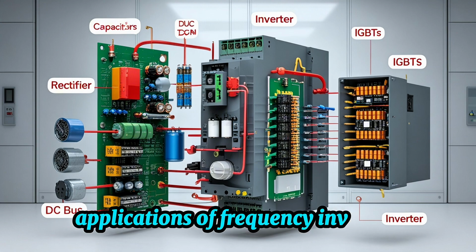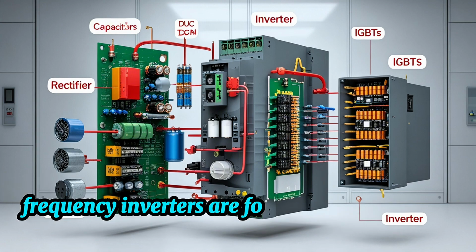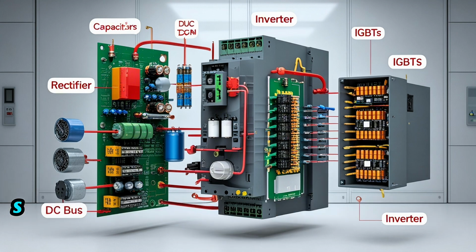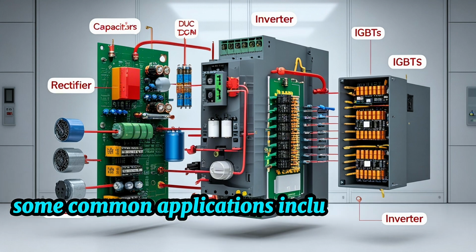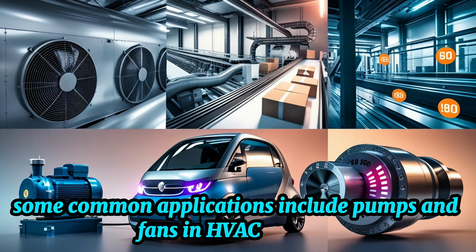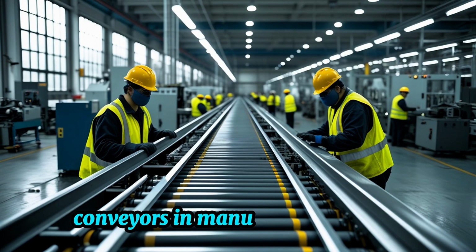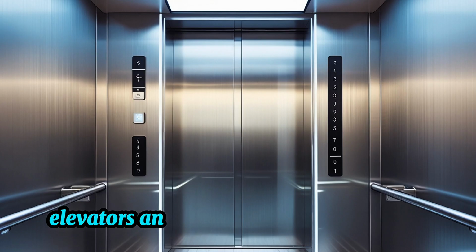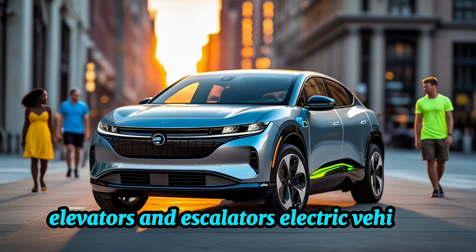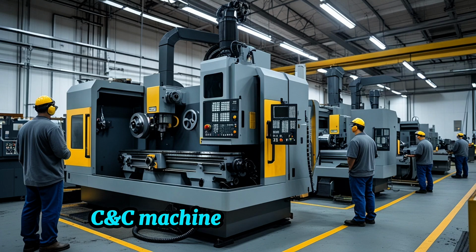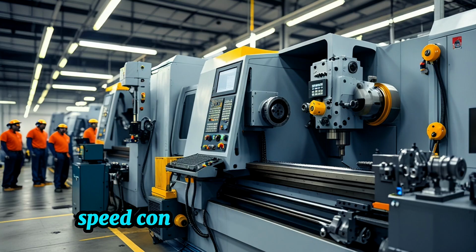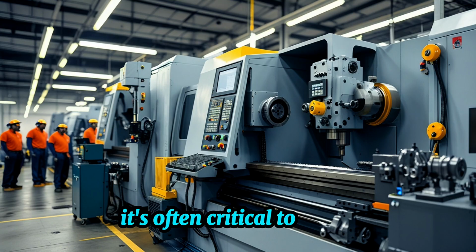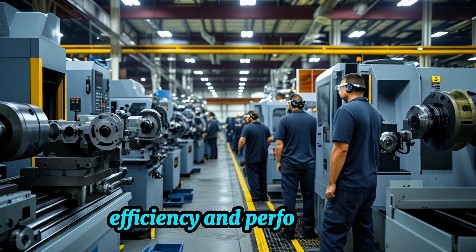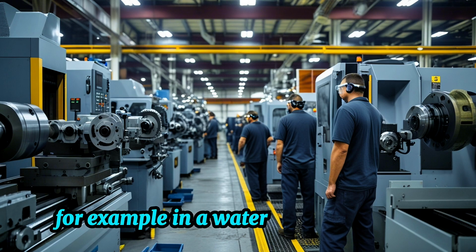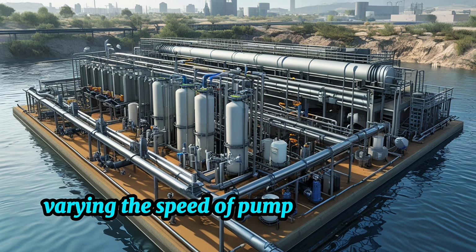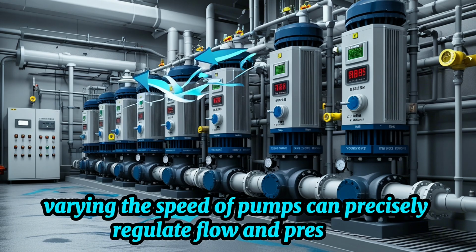Applications of frequency inverters. Frequency inverters are found in almost every industry. Some common applications include pumps and fans in HVAC systems, conveyors in manufacturing plants, elevators and escalators, electric vehicles, CNC machines. In these settings, speed control isn't just convenient, it's often critical to safety, efficiency, and performance. For example, in a water treatment plant, varying the speed of pumps can precisely regulate flow and pressure.